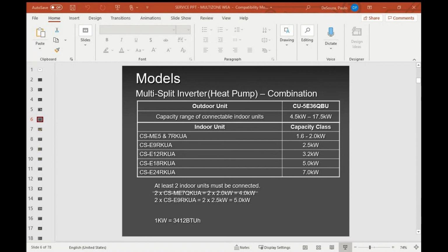So please keep in mind the two indoor units that you pick, you will always have to pick based on minimum and maximum capacity. However, if you call me and tell me, Paul, I have these two indoor units that I'm installing now, but later on I plan to install another 2 indoor units or another 3 indoor units, depending on the outdoor unit model, you can do that. And there is a trick to do that. And I can explain to you the day you have this issue. I don't want to explain it to you today because you might get confused and it can be a problem. So if you have a job site and you want to use 2 indoor units for now, and the 2 indoor units that you plan to use are below capacity, give us a call. We will explain to you how to do it.